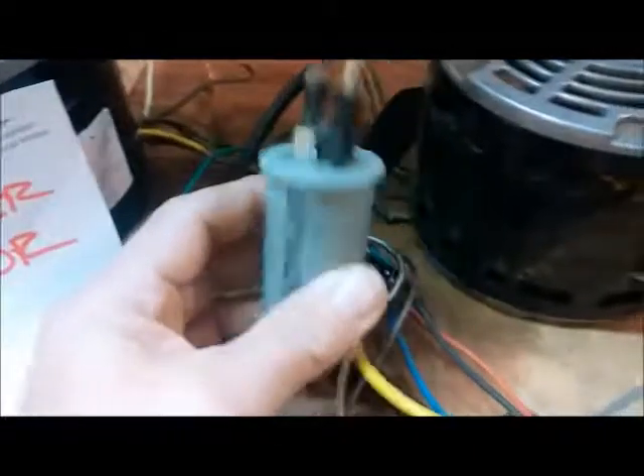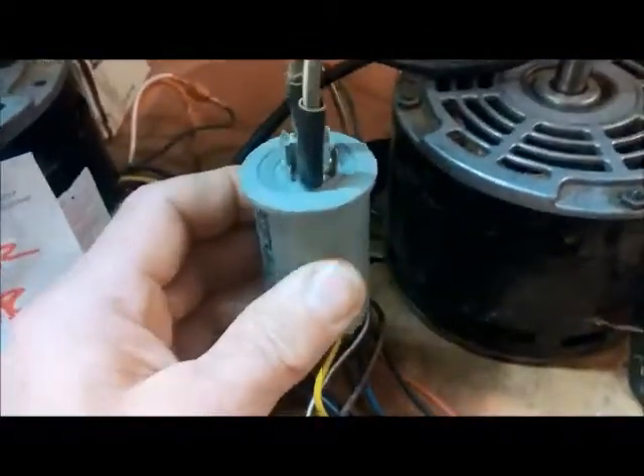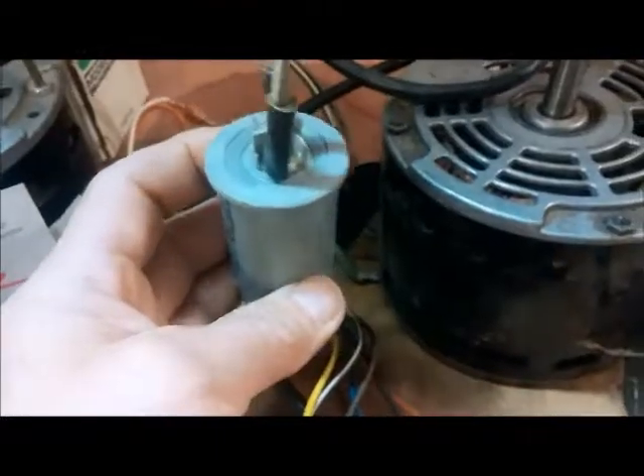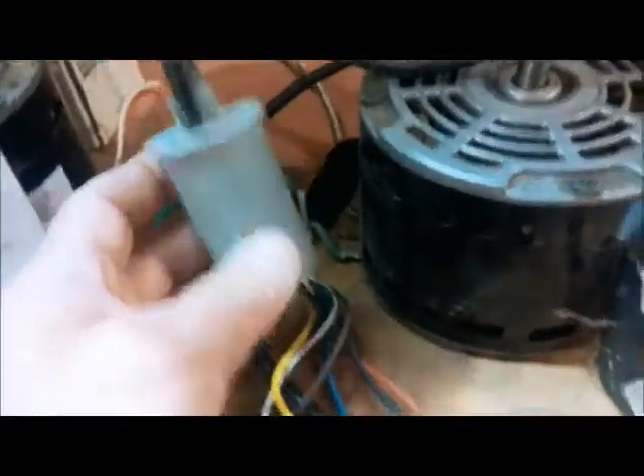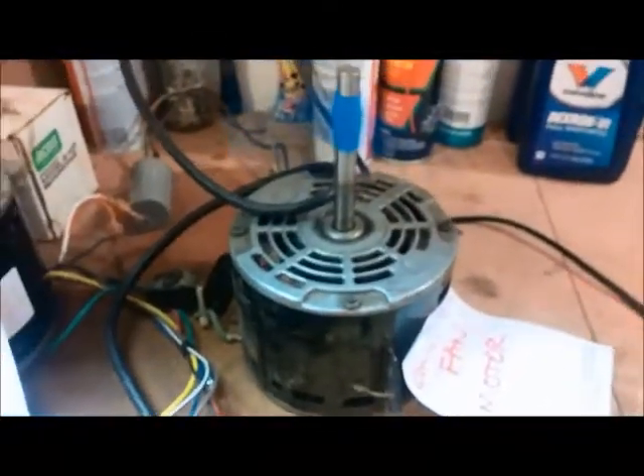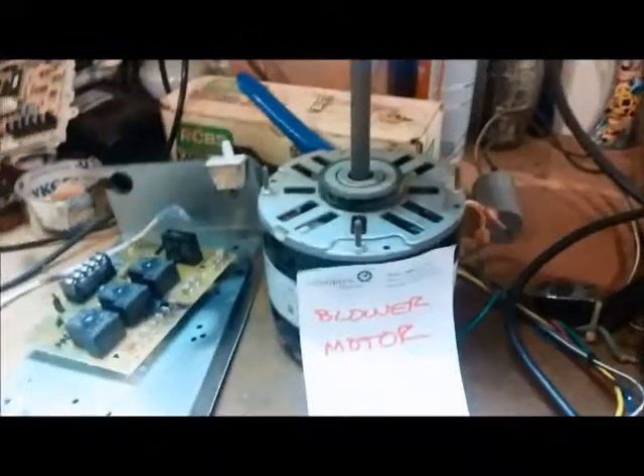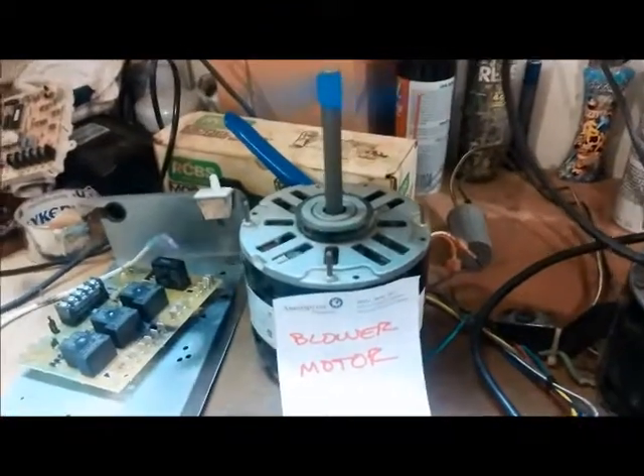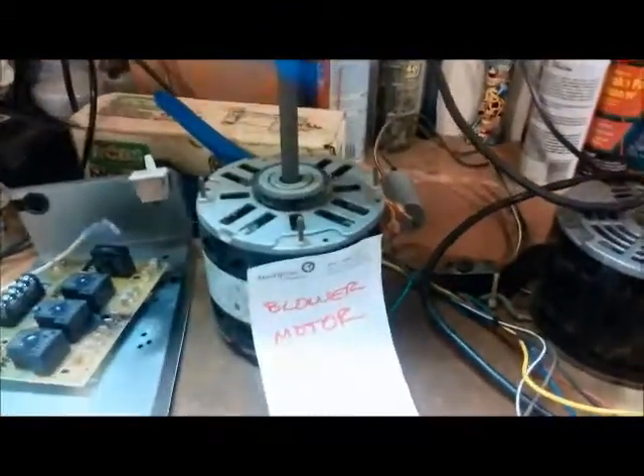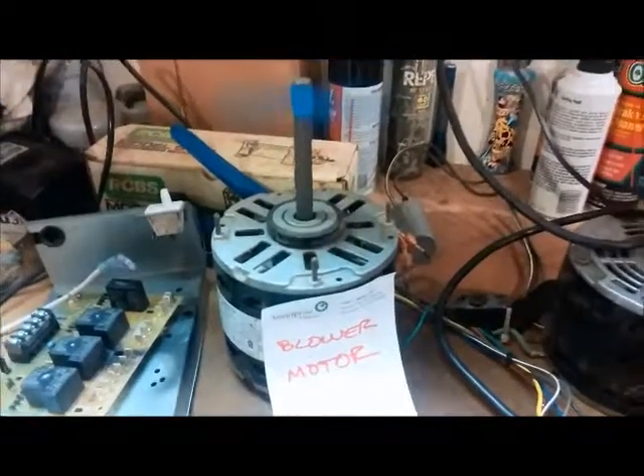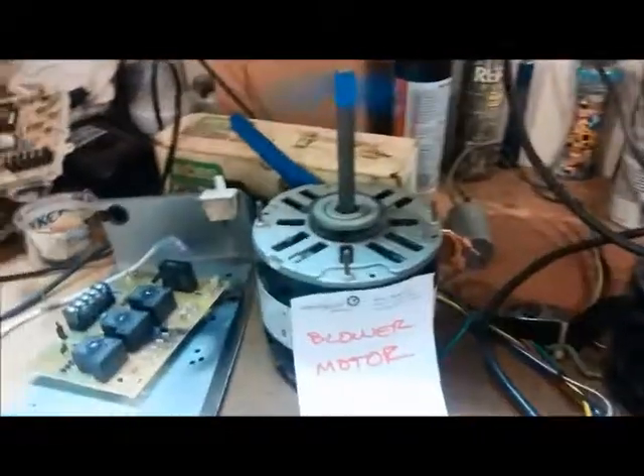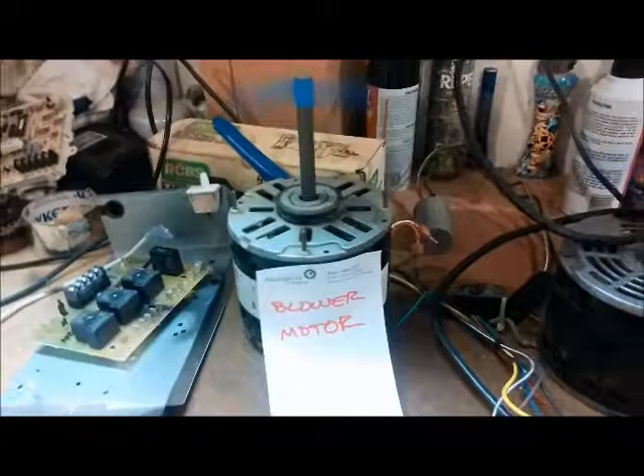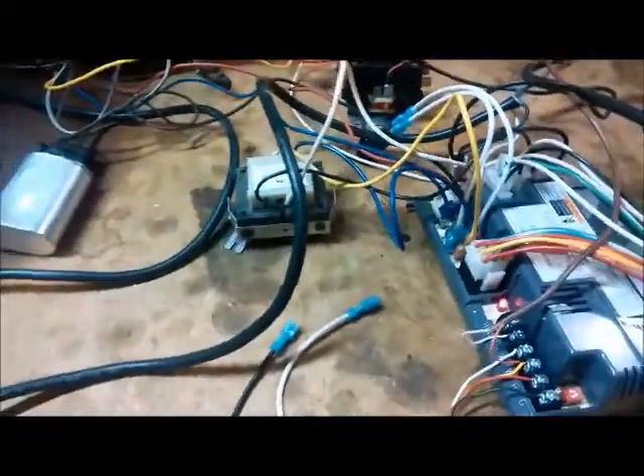So if you see a bloated or seeping oil soaked capacitor, that's more than likely your problem. If one or both of your motors aren't running, and of course the blower motor should be running. If that's not running, you're going to have low suction pressure and you're going to get a freeze up immediately. You'll see white frost on the suction line or the big line at the air conditioner. So that's a call for cool.